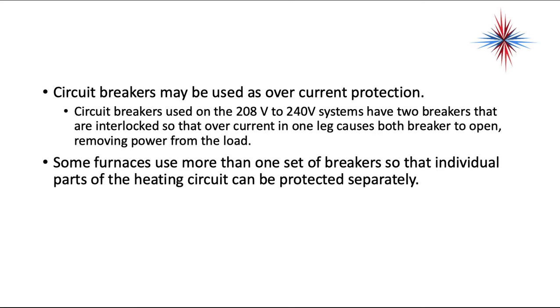Some furnaces use more than one set of breakers so that individual parts of the heating circuit can be protected separately. Always look. Make sure that you do not have power, and the only way you're going to do that is to have a meter that you have checked all the points with before you touch anything inside a furnace. It may appear to be off, but one leg may still be hot.